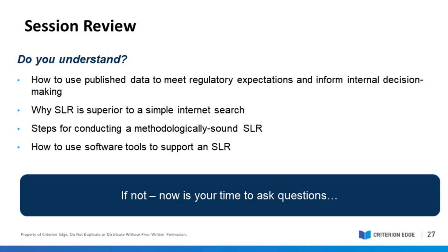Well, I suppose if you're updating a CER and the search from a previous CER was run just a couple of months before, you wouldn't need to update the search again. But I think maybe the heart of this question is that we are almost consistently asked to update existing CERs. And in our experience, the question of whether we need to rerun the search often comes up when we're scoping the old CER for the new CER. A rule of thumb is, if that prior search is more than a couple of months old, 3 months at the max, you better be thinking very hard about doing minimally a bridge search between where the old one left off and your current date, or cleaner than that, just rerunning an entire search, because then your methodology is intact across all of the results. So the answer to the yes/no question is essentially yes.